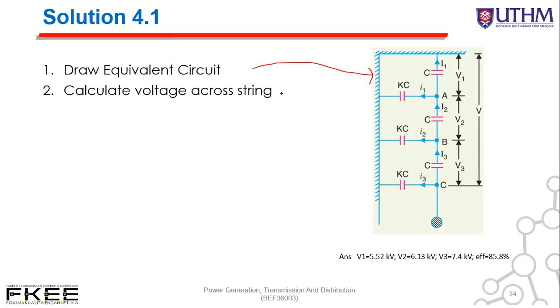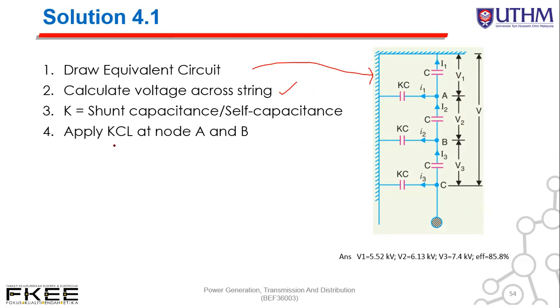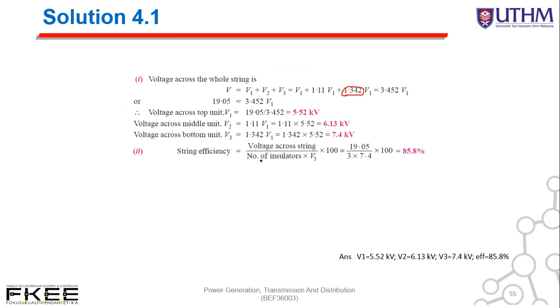Second, calculate the voltage across the string. Third, K equals shunt capacitance over self capacitance, the ratio. The best value is 0.1. Then apply KCL at nodes A and B, the same as in the previous case. Then we look at the voltage across the whole string. V equals V1 plus V2 plus V3. V1 is V1. V2 is 1.11 times V1, that is 11% more than V1. Meanwhile V3 is 1.342 V1, which is 11% more than the original V2. So we get V equal to 3.452 V1, or 19.5 equals 3.45 V1.